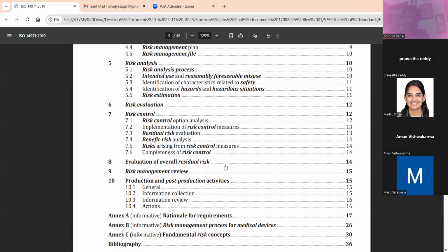I'll go in depth on how to write the severity and the occurrence. There's a very classic document which is not there in this 14971, but there is one document which I read long back on how to understand occurrence and risk. And you need to sum up all your residual risk here, the overall residual risk. Then you need to say, this is one area.